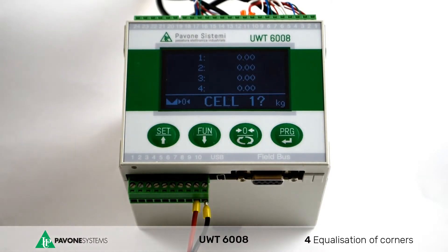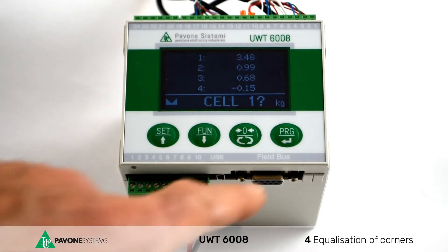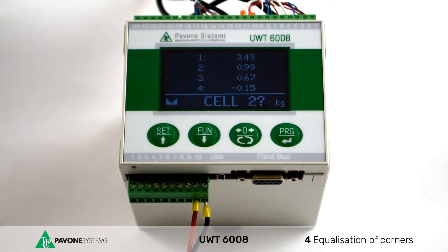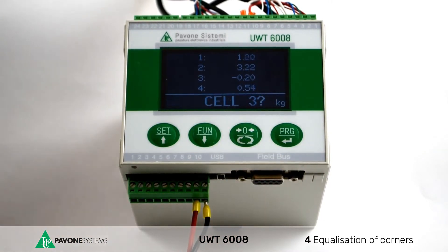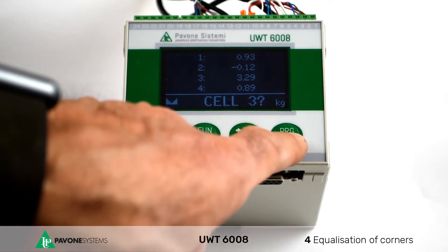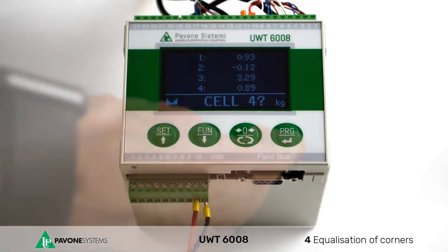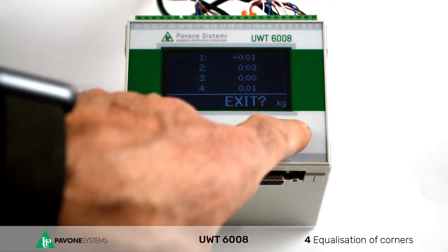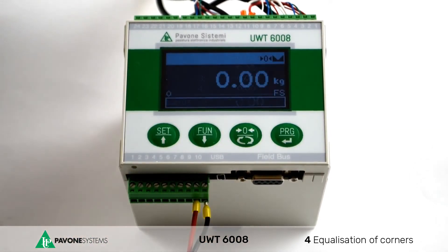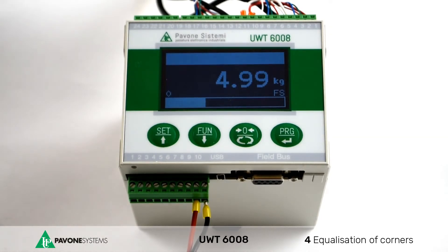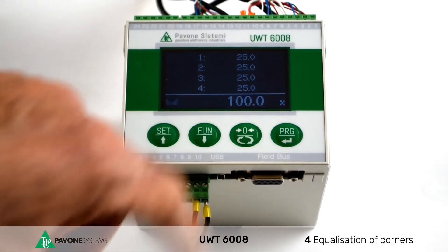As indicated on the display, apply the load on load cell number 1. If the system is correctly loaded, you will see that channel number 1 weighs more than the others. Move the sample weight to load cell number 2 and confirm with PRG. Repeat the same process for the other load cells. Once you have completed the weight acquisition procedure, confirm with PRG and close the menu by pressing the zero key multiple times. Save the changes. If the equalization was successful, you will receive the same weight value on all load cells. If you place the load in the middle of the system, you will notice that the load is evenly distributed.